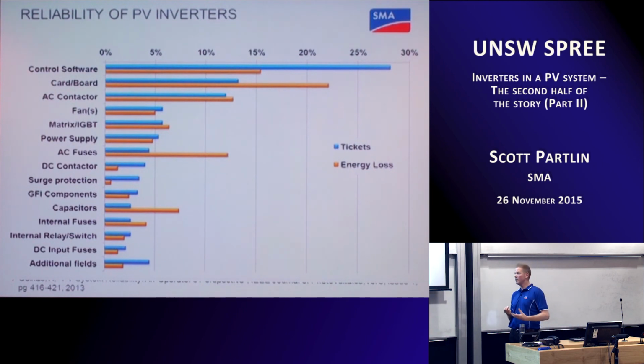When you drill down and look into the inverters, I mentioned that inverters are a complex part of any solar system, whether it's residential, commercial or utility. These are all the bits and pieces within those devices that can fail. This graph probably skews results a little more towards central inverters and utility scale power plants, because things like control software will typically be upgraded throughout the life or operation of a central inverter plant, whereas at a commercial or residential scale they may not be upgraded.